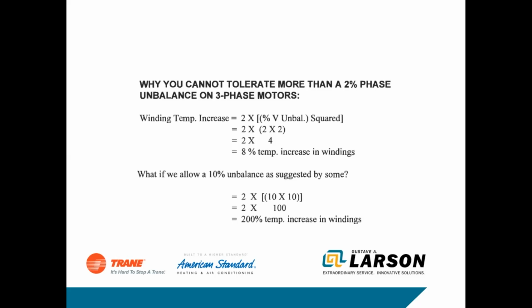If you have an imbalance of 2%, it means that your windings are going to run at 8% temperature increase in the windings for every 2%. So if I've got a system that's 10% off, as far as balance, if you do the math, I'm going to have a 200% temperature increase in my winding.